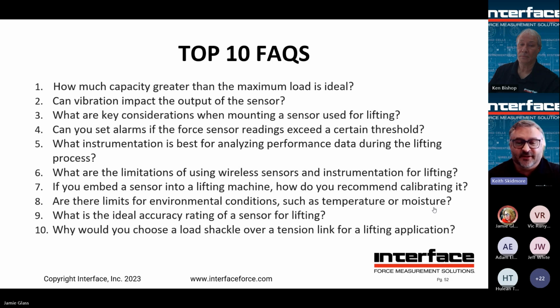So imagine if, say, a load cell is hard mounted, and then you have a sling or something attached that's coming off at an angle, that won't work very well. It's creating a lot of bending loads into the load cell. It's not going to measure accurately. So again, you maybe want a rod end clevis on each end of it, for example, so that it can self-align. Obviously, something like a load shackle or a tension link has that feature built in, or it wants to self-align.